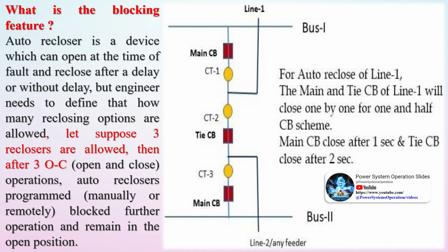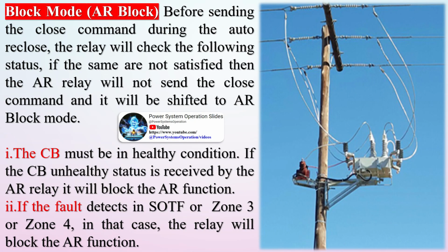If the fault is persisting in the transmission line, then the distance relay detects the fault again and it will trip all the 3 phases of the circuit breaker to isolate the line permanently from the substation bus. In this auto-reclose function, the tripping or outage of the transmission line can be avoided at the time of the transient fault. The use of auto-reclosers brings many benefits for network operators, not the least of which is that it minimizes the power interruption time resulting from faults.